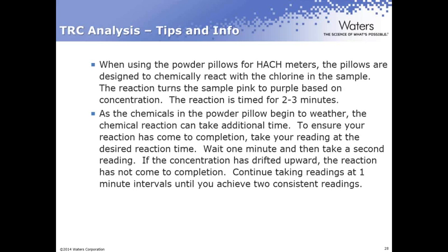As I bet some of you have noticed in the past, you take that reading, you turn around, you look back at your meter, and all of a sudden you've got a higher value on there. The reason you're getting that is because the chemicals over time will begin to weather, which means it takes a longer time for that reaction to happen.